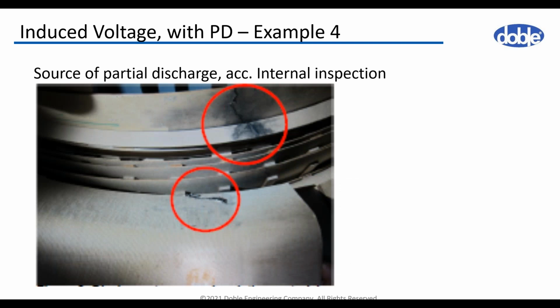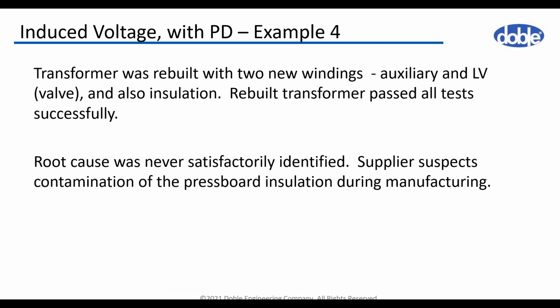Actually, there were two places indicative of a problem. One was very close to the core, and the other was related to the high voltage winding. And there were no other fault areas found within the active part. This correlated very well with the location indicated by the acoustic measuring system. Unfortunately, we were not able to identify the reason for the problem in detail.